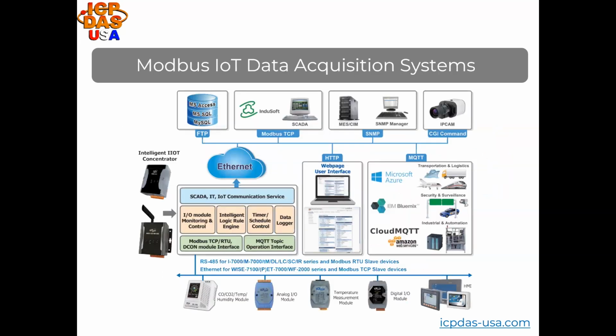Modbus IoT data acquisition systems typically consist of hardware and software components, including sensors attached to Modbus communicable data acquisition modules, which are connected to networks through serial to Ethernet gateways, Ethernet switches, and our wireless equipment. IoT equipment like our WISE 5231 connects to Modbus data acquisition equipment and can be configured to implement control logic and pass the data back to SCADA control and data acquisition systems. The data can go to cloud systems or directly back to a SCADA system.